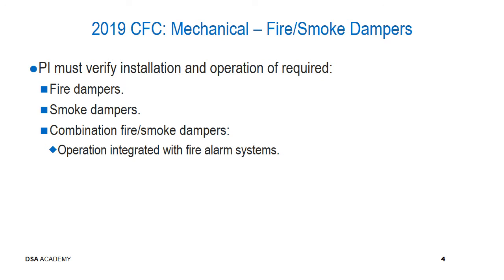Section 7.5.3 also notes that the acceptance testing shall include the closing of the damper by every means. If the damper is equipped with a fusible link, it is not required to activate the link by heat to test the damper. Visual inspection should be made after a fusible link has been reinstalled to ensure it will not impede the closing operation of the damper.